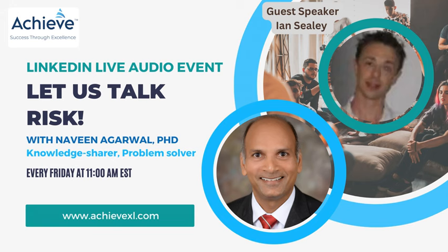But I always, in fact, I've been teaching a very important class for some regulators the last couple of weeks, and I got one more coming up. But I start out with, you need to understand the definitions of the terms you are using. I didn't use the Oxford dictionary, Ian, but I went to the Cambridge dictionary and found that there's 17 definitions for the word risk. And none of the definitions are the one in 14971. So if you're going to use 14971, you have to use that definition. And you need to go there and read that and understand it.